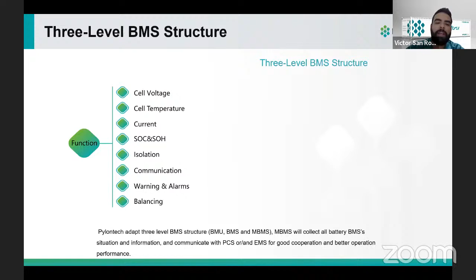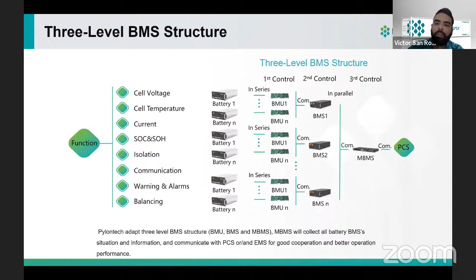If you work with the storage system, you should know that the BMS is the battery management system. It's like the brain of the battery. With these three levels, we can do the BMS of each battery module, then going for the controllers of the batteries, and we can have a master BMS that handles the controllers of each battery bank. So with this three-level BMS, we can be sure that the system works properly in terms of voltage, temperature, whatever. So this is what it means.